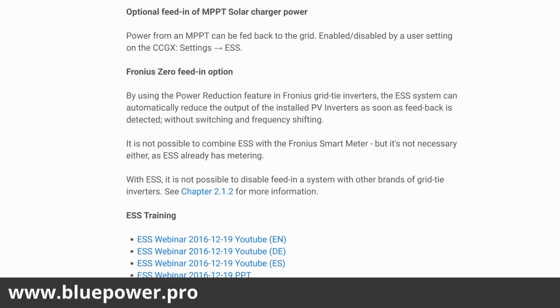Fronius zero feed-in option. By using the power reduction feature in the Fronius grid inverters, the ESS system can automatically reduce the output of the installed PV on the system. That's only achievable if you've got the Fronius inverter connected on the output in this scenario, or if it's on the inputs and you have a grid meter connected. In this case, it's only on the output, so the inverter is able to measure all the loads and whatever it is feeding back into the grid.